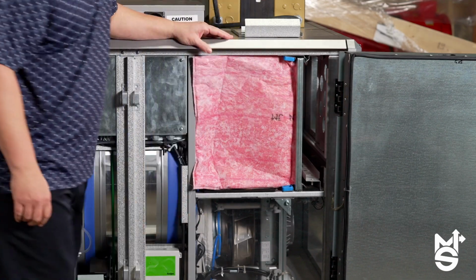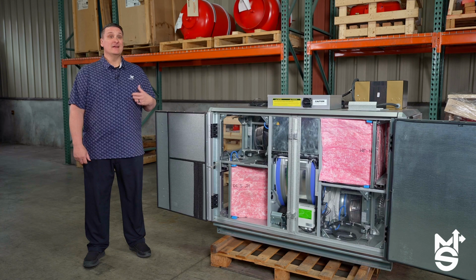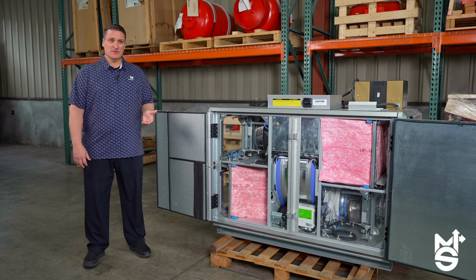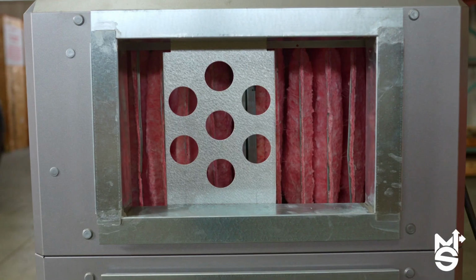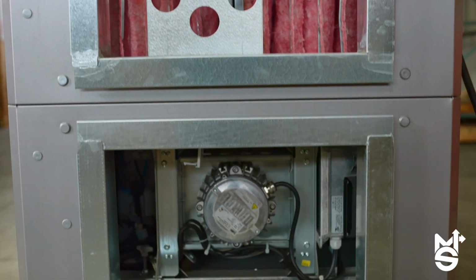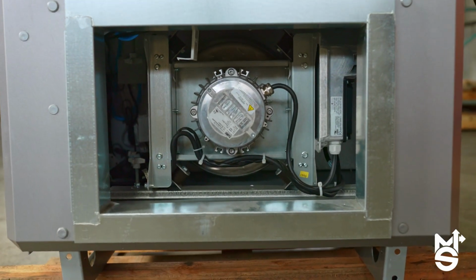Both the main filter and pre-filters come with pressure drop transducers. They are calibrated at startup, continually monitored, and calculate the adjustments made in order to maintain accurate airflow as the filter loads. This provides optimized building ventilation. The filter points include programmable set points, and they allow the operator to be notified via alarm by the DDC system or perhaps an email server.